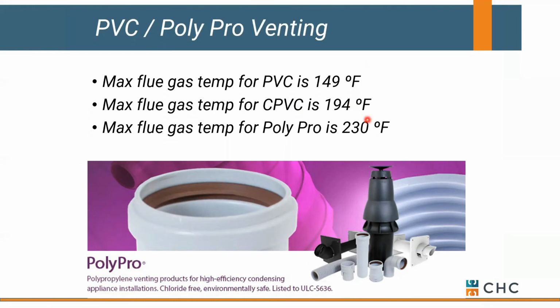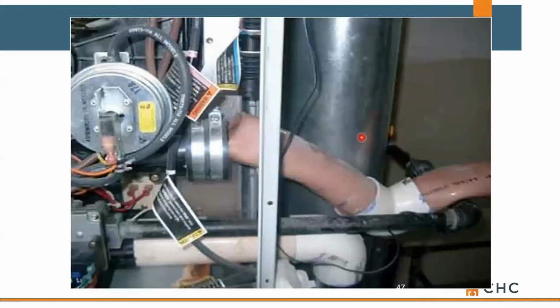So we're seeing a lot of people try to transition into Polypro, which is a tested and listed system, and it also carries a higher max temperature. When plastics get soft, it acts like spaghetti. Your 90s hold up fine, but the rest of your vent pipe gets pretty soft and saggy. Now you're blowing potentially live combustion into an open space, and that can be deadly.